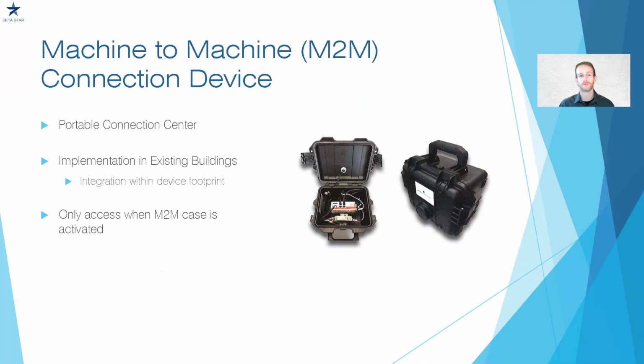The last connection point is what we call a machine-to-machine connection device. It works like a suitcase or briefcase, but it's a portable connection center with cellular technology built in. The service technician or facility maintenance team can bring this device in and connect it directly to an Ethernet port built into the front fascia, right under the HMI. This enables only on-demand access to the equipment. It's secure because it operates on a cellular signal, completely separate from the local connection, and it's on-demand since it only connects when this device is plugged into that Ethernet port on the front of the machine.